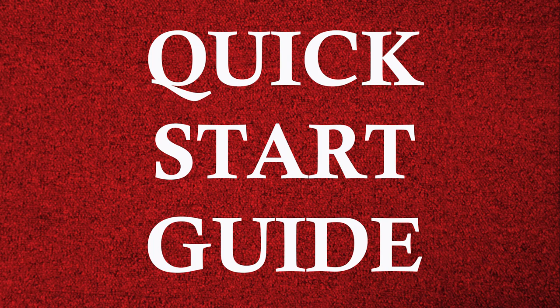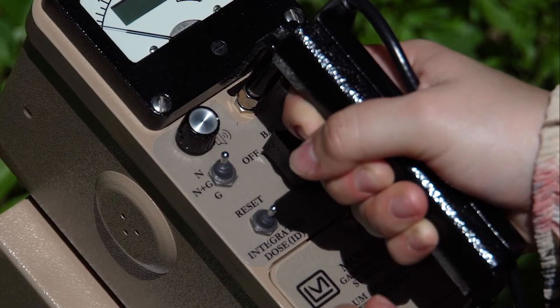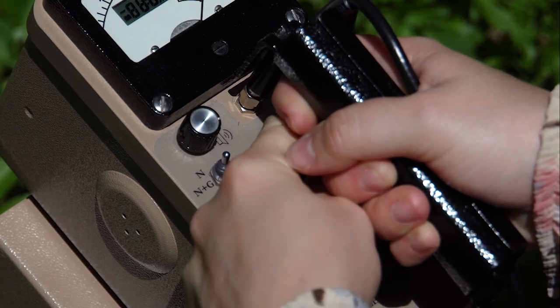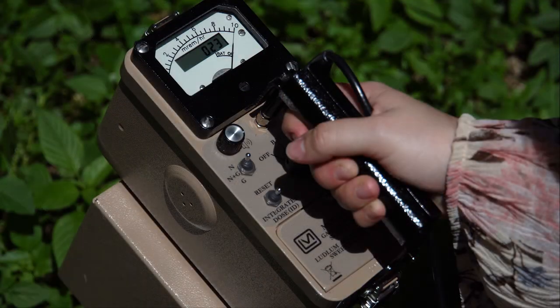Quick Start Guide: Rotate the range switch to the BAT position. The meter pointer should deflect above the left vertical mark on the BAT OK line. If not, replace the batteries and repeat the test. After passing the battery test, the instrument is ready for use.